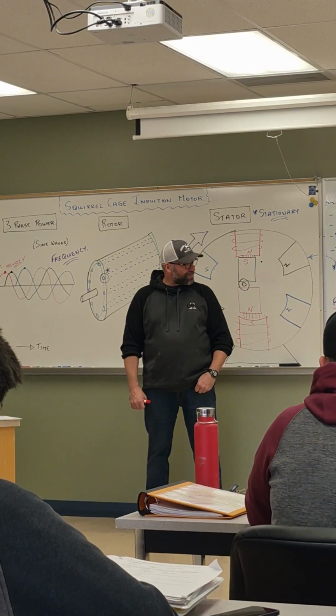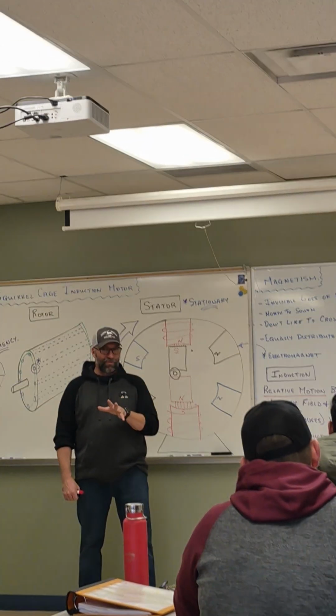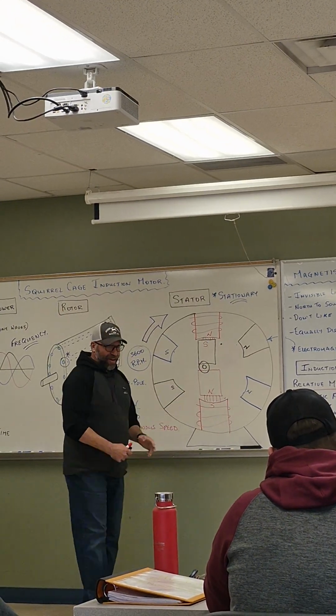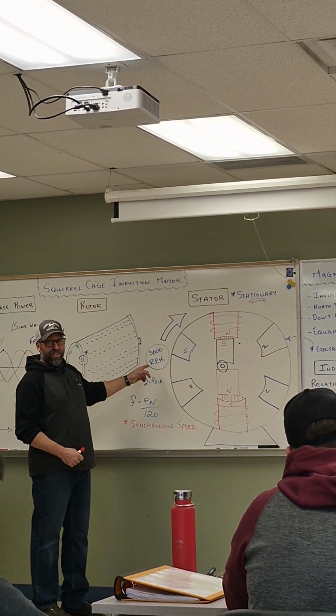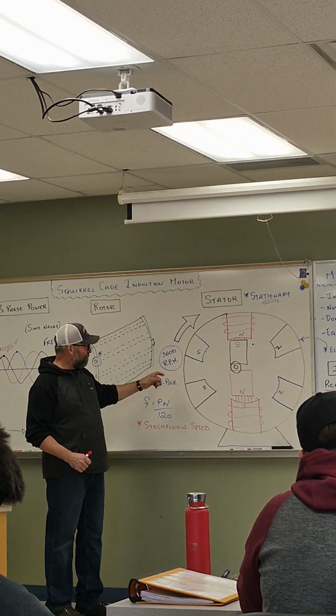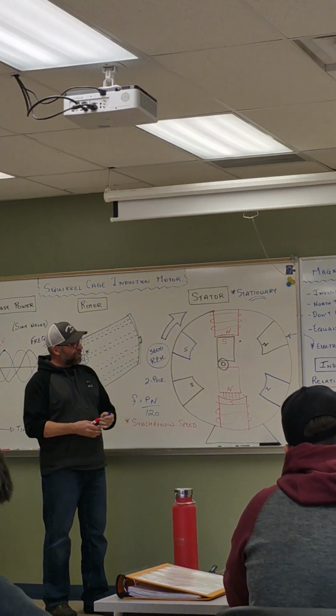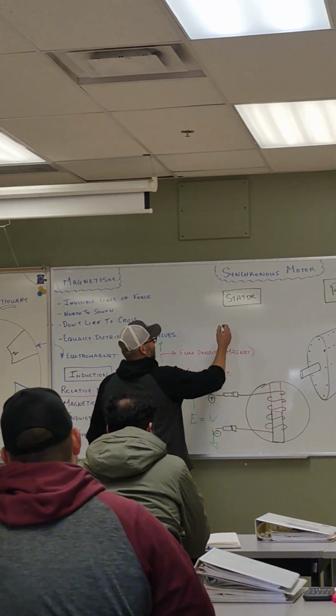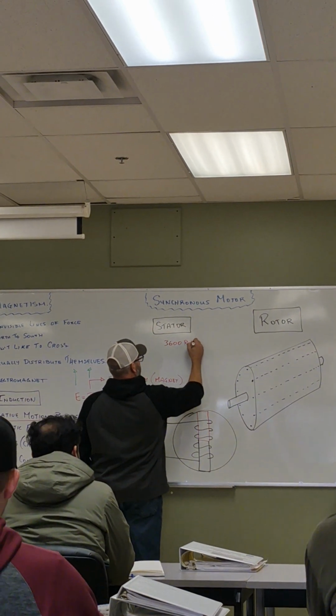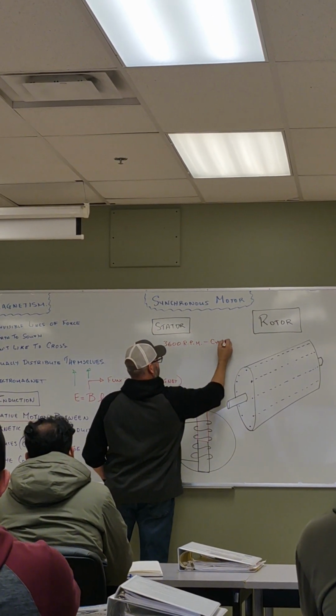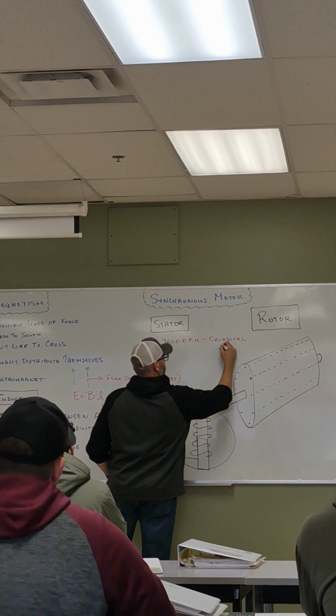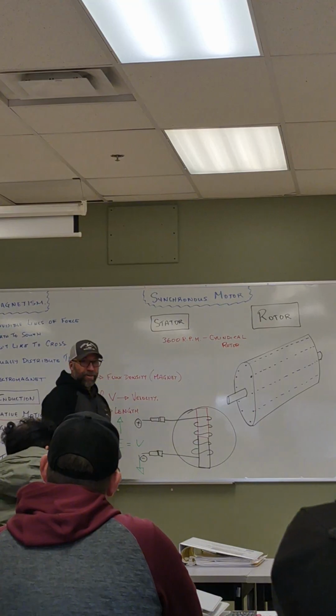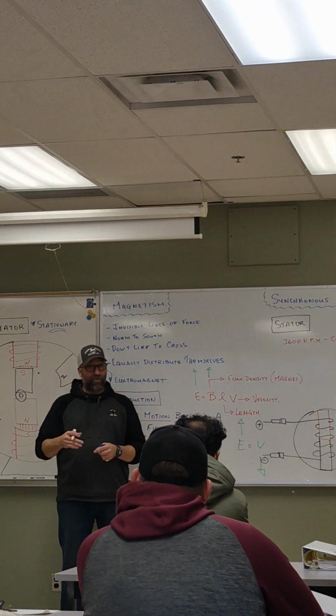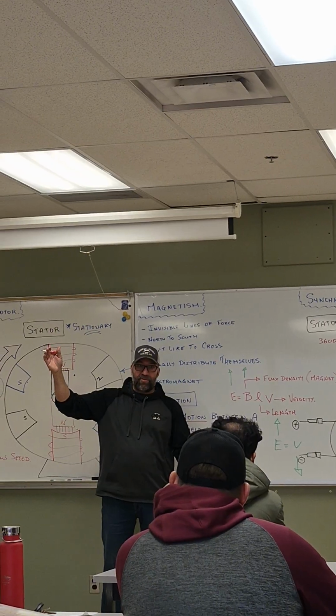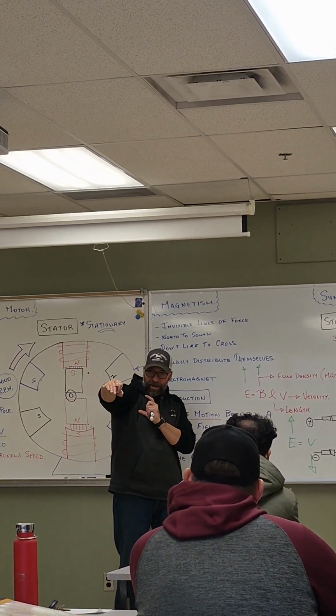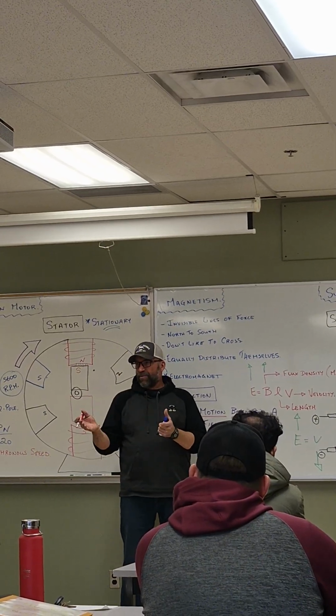Now with that synchronous motor, there are two rotor designs, and I did see that, so we're going to talk about them really quick. If that thing is going to go that fast, that's really, really fast for a motor to turn. Rotor design changes a bit. If you're talking 3600 RPM, you're talking about a cylindrical rotor. What that means is the rotor is small in diameter and long because it's spinning fast. We don't want a whole lot of centrifugal forces way out here because it's spinning real fast. So we keep it nice and tight, magnets on a long line, that locks onto the stator and away it goes. That's for high speed.